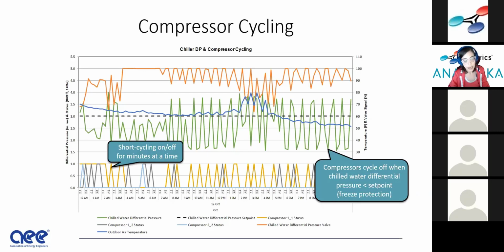Short cycling of equipment. I used to do audits, and I remember hearing pneumatic system compressors in the basement cycle on and off, and that meant there was a leak in the pneumatic somewhere. We'd go around listening for hissing through the walls. But this is short cycling of a compressor for a chiller. And here we saw cycling. It also shouldn't have been running at this time. Anyway, the chillers were cycling on and off because of the differential pressure set point. There was no deadband there, and it was hunting. And that was for freeze protection. These units never should have been on, actually, and these were turned off shortly after.